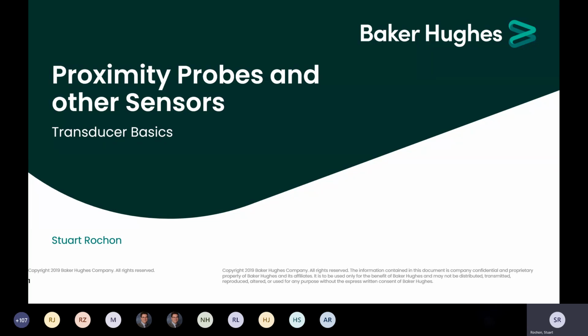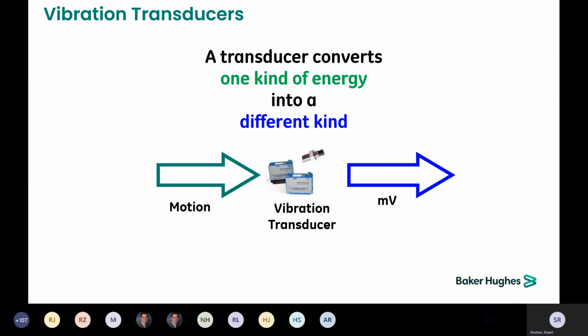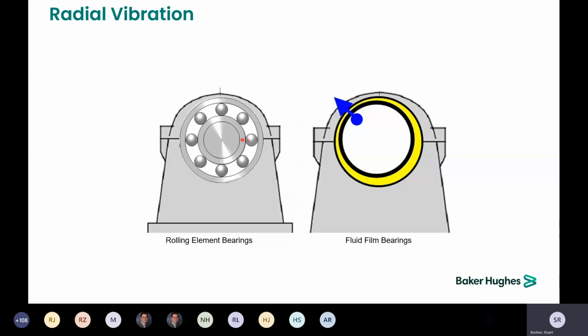So today we're going to be covering proximity probes and other vibration sensors. Vibration transducers basically convert motion into millivolts. For displacement, it's mils of displacement to millivolts of electricity. Generally, we have two types of bearings. You have your roller element type bearing and your fluid film bearing. And we monitor these generally quite differently because of the physics of each one.